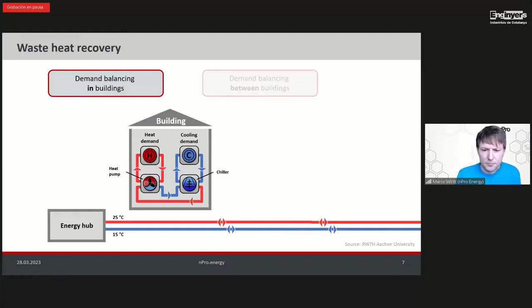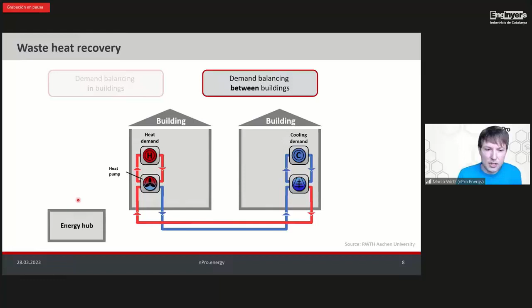If we have buildings with different usage types, for example maybe one building is a data center or a public swimming pool with too much cooling demand, we can use the waste heat and feed it into the network. Another building which needs heat can then use it as a heat source for covering its heating demand. That's the second effect, balancing between two buildings. This means the load at the central heat source, like a geothermal field, decreases, and we need less borehole meters or less heat sources overall.